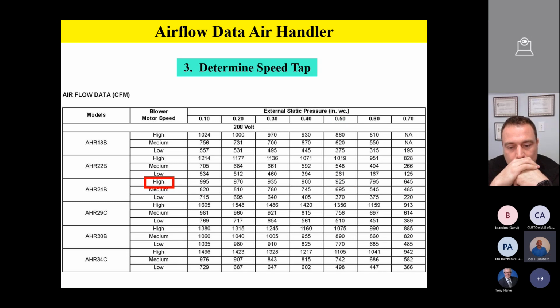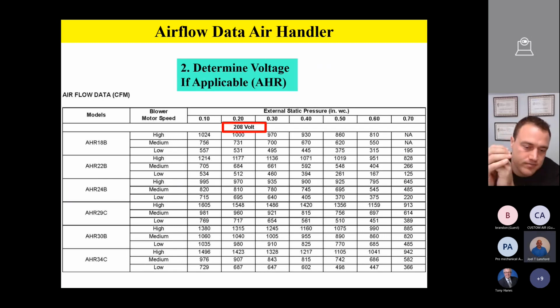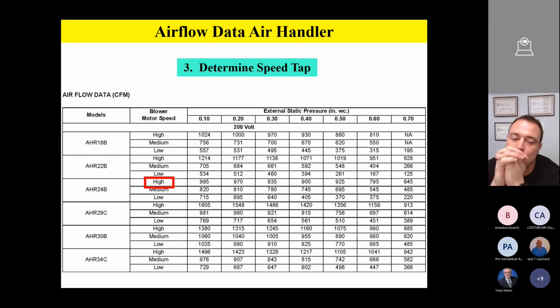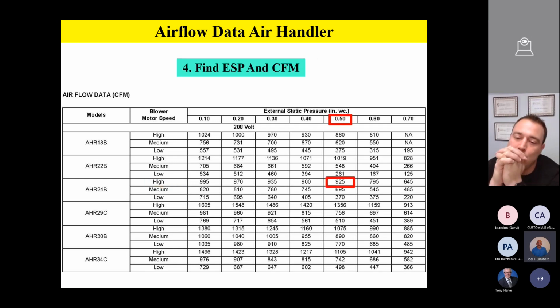So in this example here, let's back up one more time. So I have an AHR 24B air handler, and I actually take my voltage rating on the job, and I see this 212 volts. I'm just making that up. So I'm going to use a 208 volt chart. I take my static pressure reading. I see that I'm on the high speed tap. I've got 0.50 inches of static pressure total. And I correlate that down, and the actual airflow I'm moving through that cabinet is 925 CFM.